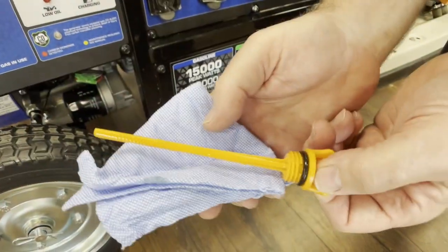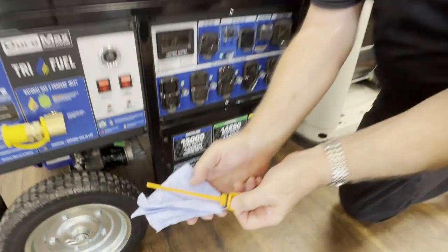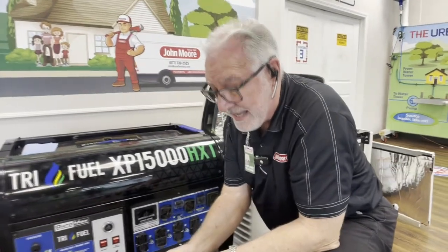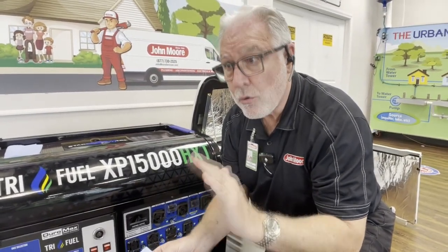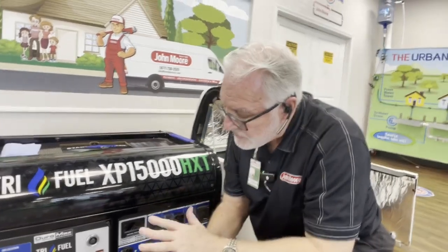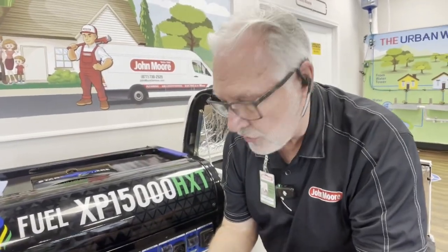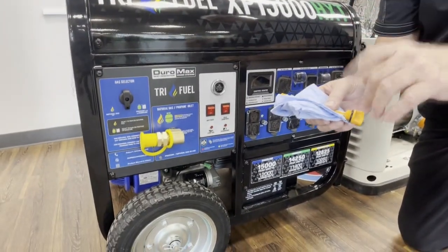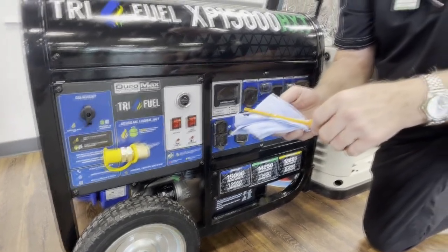So you want to make sure when this is running, about every 8 hours, check the oil level, and every 50 hours, so 2 consecutive days of running, replace the oil. Because there's no radiator or engine coolant, these things run very hot, and they run at 3,600 RPMs. Most cars are running at 2,000 RPMs, so you're building up heat quickly. So you want to make sure you replace the oil after 2 days of continuous running to ensure the oil hasn't broken down.